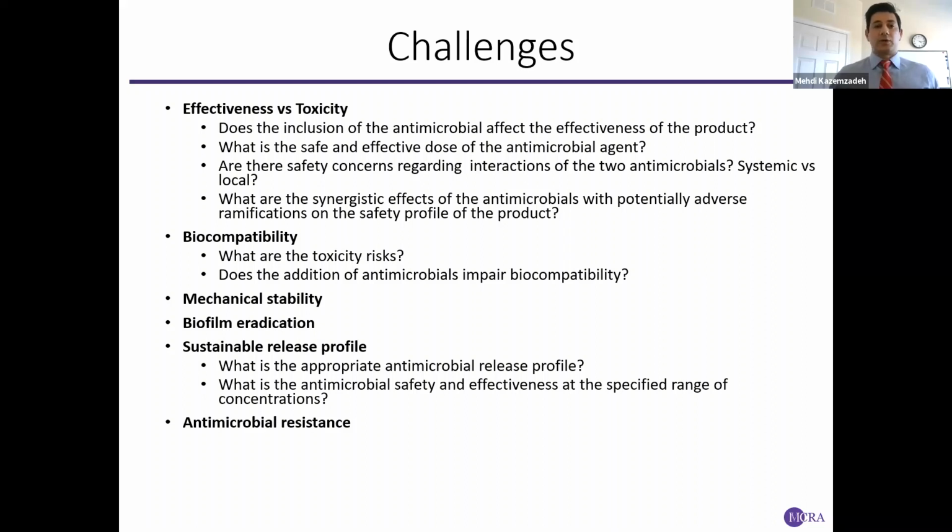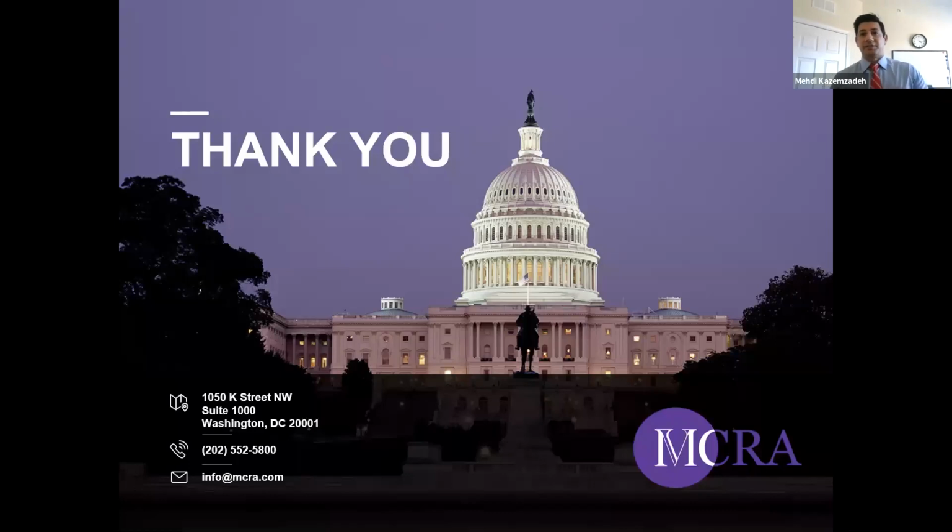The addition of the antimicrobial properties should not interfere with the mechanical stability of the orthopedic devices. There is a difference between biofilm eradication and antimicrobial property. A device that is claimed to be combating biofilm should show that it can destroy the matrix of biofilm. Also, the antimicrobial coating should show that it has a sustained release profile and that it doesn't develop antimicrobial resistance. By this, I conclude my presentation. Thanks for your attention.